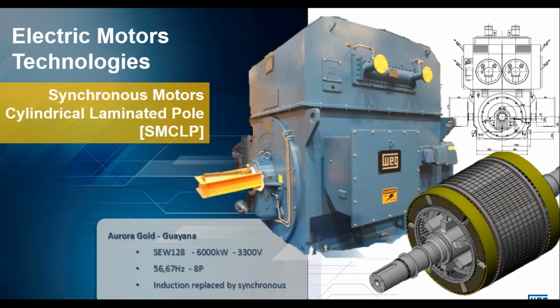So one important thing to consider with this design is that the rotor construction, being perfectly cylindrical, creates a uniform air gap between the rotor and the stator. Also, the damper cage, which is the squirrel cage construction that allows this motor to self-start, is also symmetrically placed, embedded into the excitation winding. Those two facts give this synchronous motor an advantage: because the air gap is constant, you don't get an oscillatory torque known as reluctance torque, which is quite common in other synchronous motor designs.